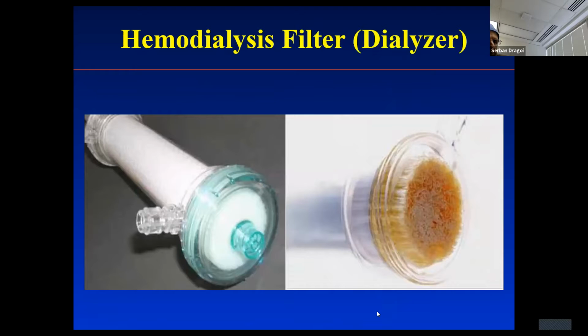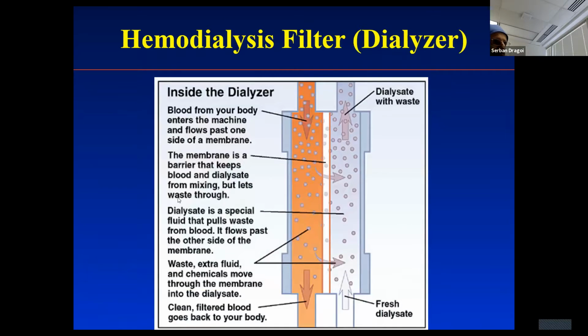So that's how these dialyzers work this day and age. And of course, here is another view. This is all this semi-permeable membrane, the fresh dialysate, the toxin-rich blood, and the way this exchange takes place.